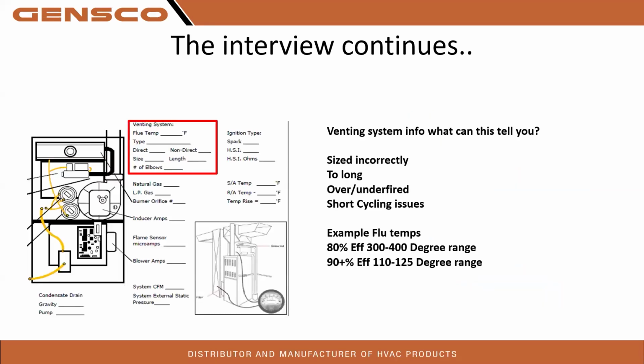All right, so venting system. What does this tell us, right? Of course, it can tell us if it's sized incorrectly, maybe too long, overfire, underfire, any kind of short cycling issues. So is it direct vent, non-direct vent? What's the size? How many elbows, right? Because we have to account for elbows, especially at 90%. What's the flue temp? What is that flue temp telling us?